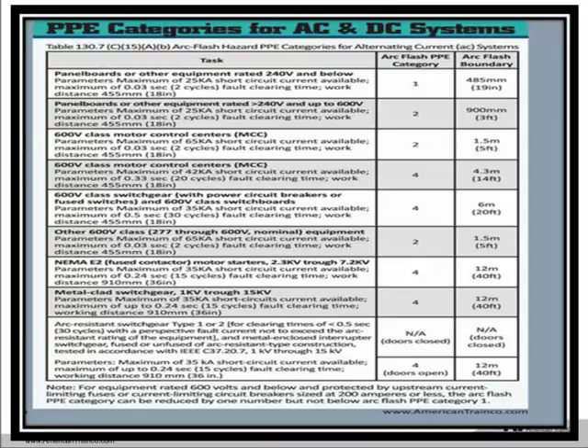And this table is going to be used in conjunction with some parameters. And these parameters have been in 70E since 2004. So if I walk up to a piece of equipment, and that piece of equipment is 240 volts and below, and the fault current is 25,000 amps or less, if the clearing time is 0.03 seconds or less, then I can use this table. If I cannot satisfy those parameters, I am going to have to do an arc flash risk assessment. So I would have to go to the analysis method unless I can satisfy these parameters.